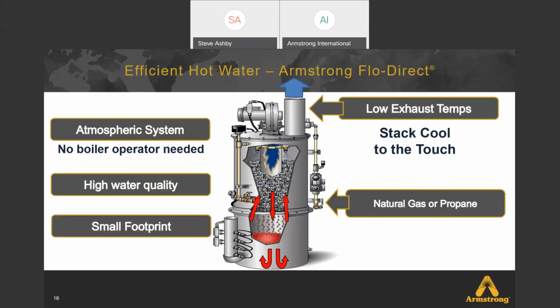Talk a little bit more about direct contact heaters. They're atmospheric, so no boiler operator required, no permitting for installations. It's an atmospheric piece of equipment. The water quality is high. So for coming in contact with process equipment, for washdown, water quality remains high. As far as overall dimensions, typically this will be smaller than steam boilers. A lot of the footprints can be pretty minimal depending on the particular design.